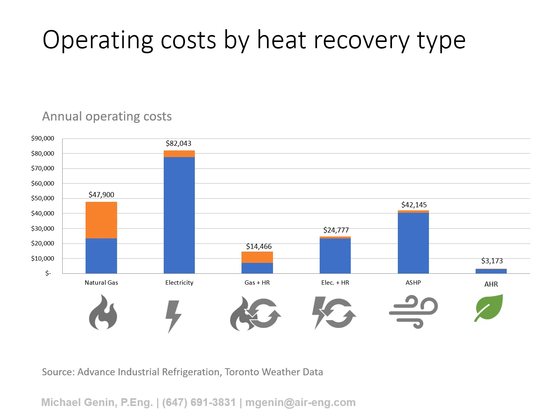So the blue indicates the direct fuel cost, and the orange indicates a carbon tax added to that fuel. If we were to heat that with straight up natural gas, it would cost $47,000. If we were to heat the same airstream with electricity, it would be $82,000. Then we have gas plus a 70% effective passive heat recovery device. This might be a heat wheel, for example, $14,000. Electric plus the same passive energy recovery device, $24,000. An air source heat pump, which could be used to generate hot water and then taking that hot water to heat the ventilation air, $42,000. And then active heat recovery at just over $3,000.